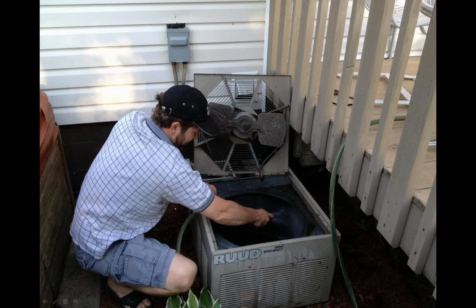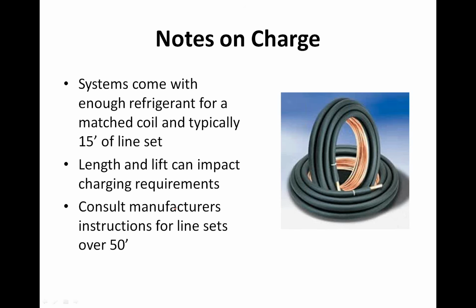Think about your refrigerator at home. If your refrigerator wasn't cooling well, I hope nobody would grab a piercing valve and check the charge to see if it's out of refrigerant, right? Everybody knows to get the vacuum out, vacuum underneath it or behind it, clean it out, and make sure that if we've got filters, the filters are clean also, right? We're going to make sure all those things are done first so that the system can operate at its optimal performance.